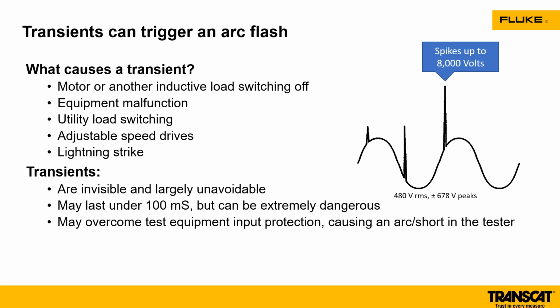If you think about it, a lot of transients are out on these lines. These transients are what's causing some of the issues with our equipment, whether it's inductive load switching off, maybe there's an equipment malfunction, maybe even on the utility load side they're doing some switching. Adjustable speed drives can cause these transients. All of those have potential issues that could cause a fault or cause a blast, even a lightning strike. And that's a very obvious one. If you think about a lightning strike, that's an incredible amount of energy going into it. These transients are invisible and they're very fast. Sometimes they happen in under 100 milliseconds, so they can be incredibly dangerous.